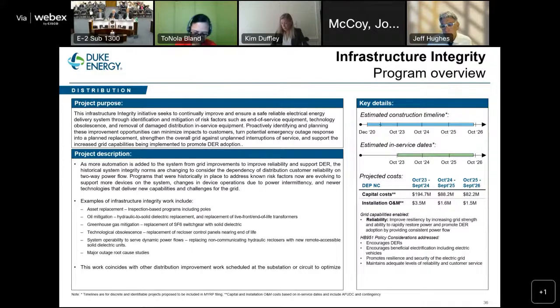Some examples of this you'll see in the program description, including inspection-based asset replacements — could be transformers that have been inspected, as well as poles. Oil mitigation, where we have opportunities to upgrade equipment from hydraulic to solid dielectric, removes oil off the system. Distribution does have some SF6 gas insulated switchgear, typically vault-mounted switchgear, that we now have the option to replace with modern solid dielectric, so we can remove that SF6 gas from the distribution grid. Technological obsolescence is another one listed there.